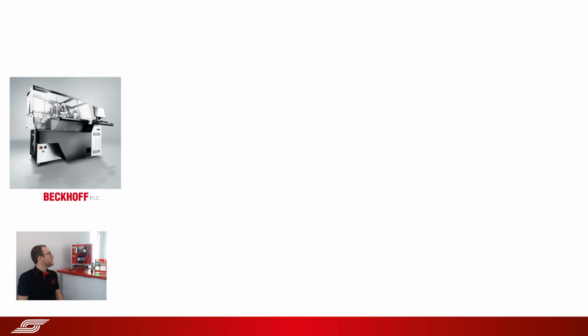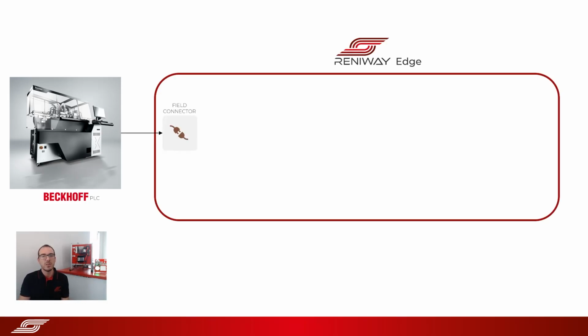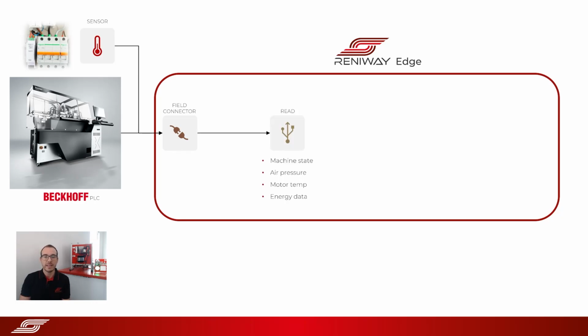For today's demo, we'll be using this live setup using a Beckhoff PLC which implements a simulated machine. We'll be connecting the PLC to the Reniway Edge platform using field connectors. A field connector is a software block implementing an industrial protocol. In this case, we'll be using OPC Unified Architecture. To show the flexibility of the Reniway platform, we'll also be adding a sensor. This is an energy measurement device which uses Modbus TCP. Once connected, we can read out different tags like machine state, air pressure, motor temperature, and energy data.